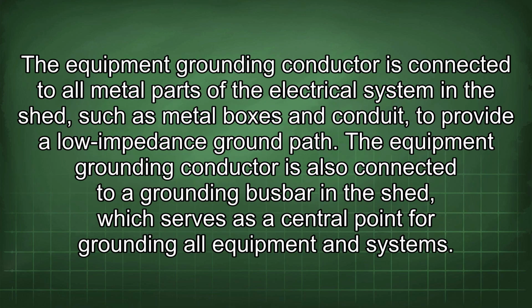The equipment grounding conductor is connected to all metal parts of the electrical system in the shed, such as metal boxes and conduit, to provide a low impedance ground path. The equipment grounding conductor is also connected to a grounding busbar in the shed, which serves as a central point for grounding all equipment and systems.